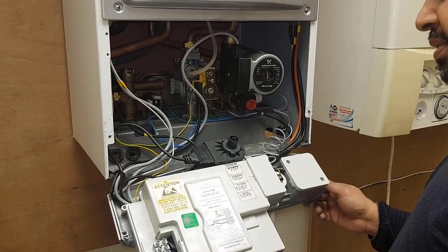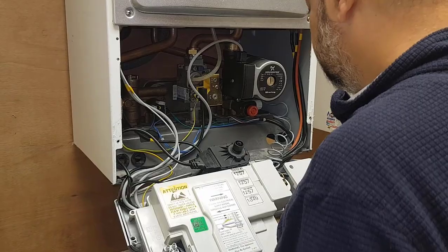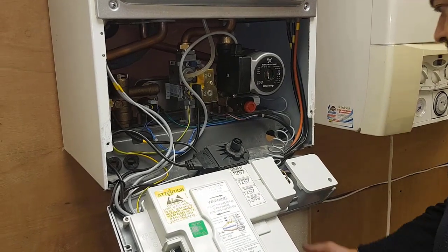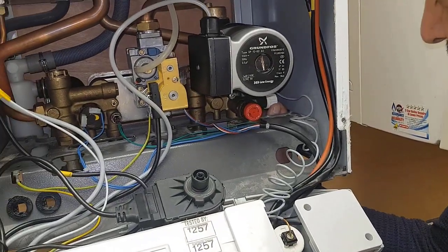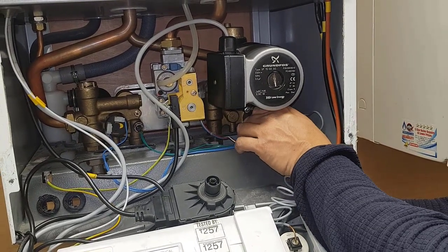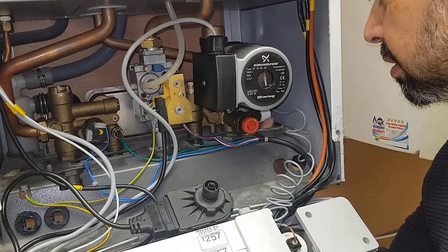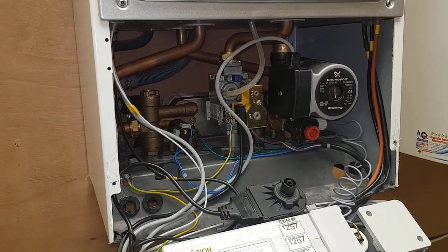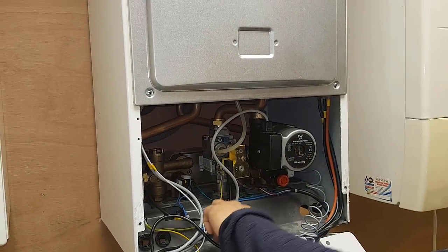Thank you. Right, so now I'm going to start doing the repair. The first thing I'll do is isolate the flow and return, and then I'll get a bucket, put it underneath, and drain the water from the drain point, because I've got access to it. If not, then I drain it through the PRV. So I'll open up the drain point, and I'll let the water drain. In the meantime, while that's happening, I'll take the actuator motor off and put it aside, put the cable aside.